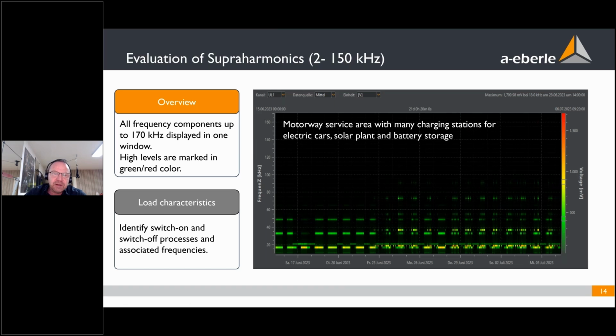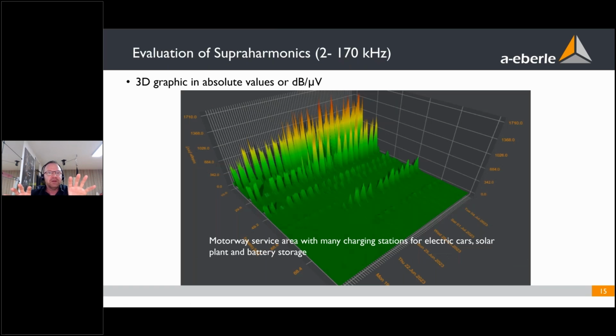The next possibility is a 3D graphic. With a cursor, you can move this graphic and look from all sides. And also here, the story is nice to see. Here we have the solar plant, and they install more and more solar inverters. So you see, our level goes up over the limits here in this network. And the motorway station has a lot of problems. They have a small supermarket. In the supermarket, they get problems with the lights.